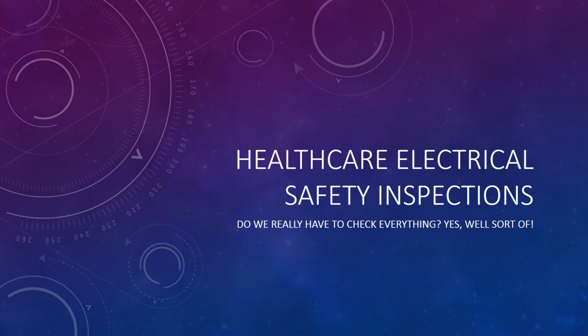Going back to a nuance I learned recently: as you read through the chapters on how to do safety inspections, it talks about ensuring a proper ground. You connect the probe on the safety analyzer to the chassis or a metal external part of the device, then plug it in, and read the resistance of the ground cord through the device back to the outlet. You want to make sure you have a very good, solid ground, meaning the internal ground is connected to the cord ground, which is the safety for everybody.